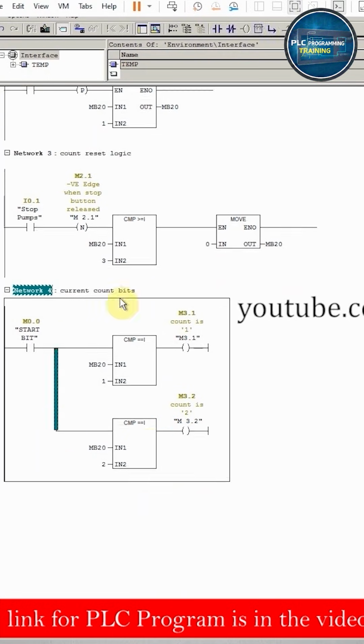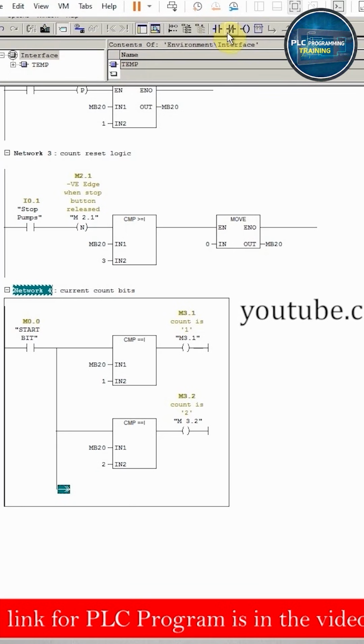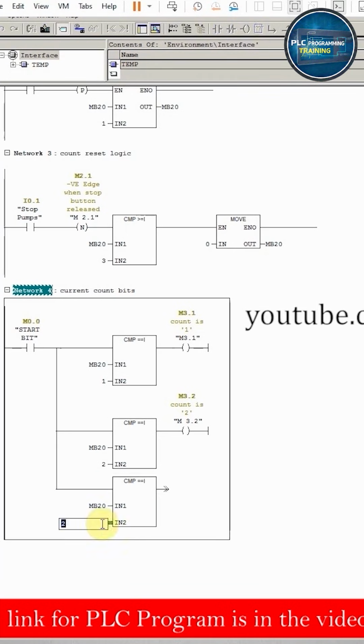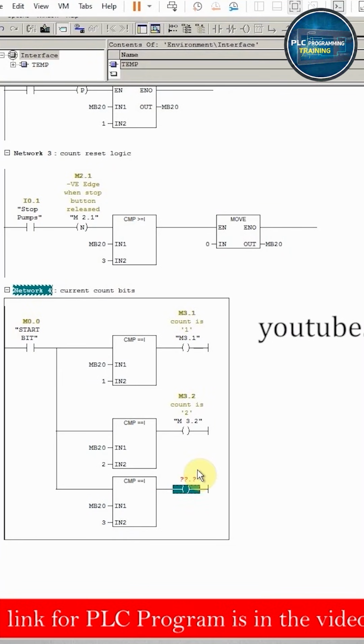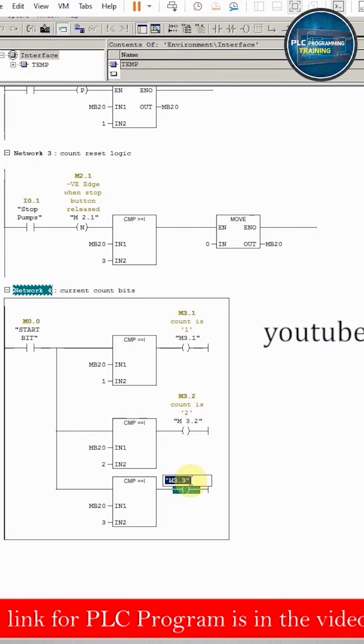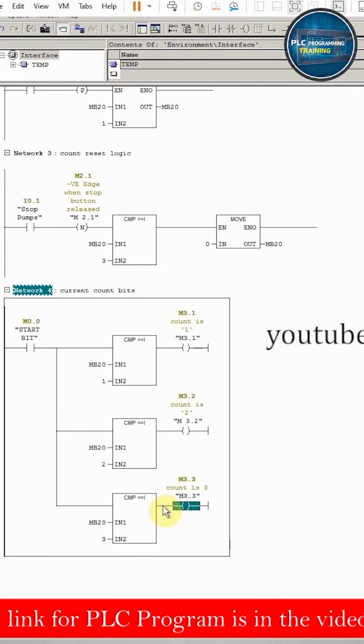Next we will insert another branch here and we will use the comparison instruction here. This time we will compare the MB20 with the value 3. So whenever the count inside the MB20 data register is equal to 3, it will activate a bit which is M3.3, and this bit will indicate that we have pressed or started the motors third time.